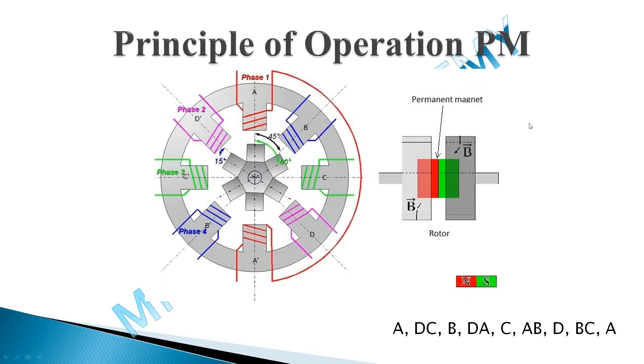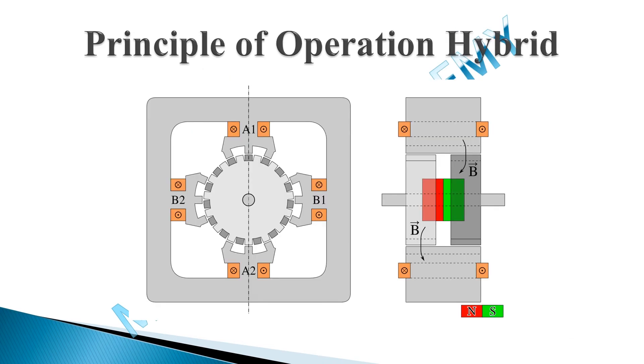The same principle of operation applies for the permanent magnet stepper motor. The only difference is that in the permanent magnet motor, the rotor uses permanent magnets instead of soft iron, so there is a holding torque. Even if a load is applied, as long as the force is less than the holding torque the rotor holds its position — that is the advantage of permanent magnet. The principle of operation is similar to variable reluctance, so I will not explain it again; only the rotor material changes.